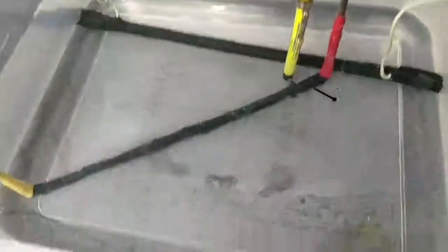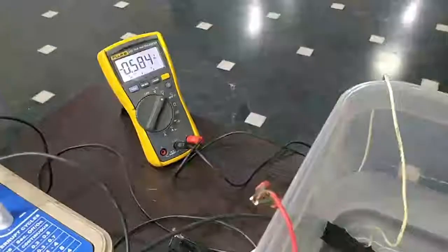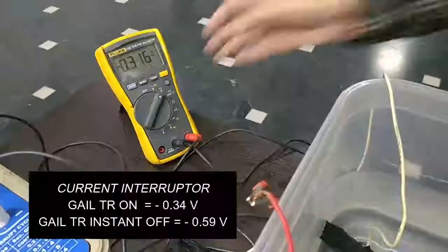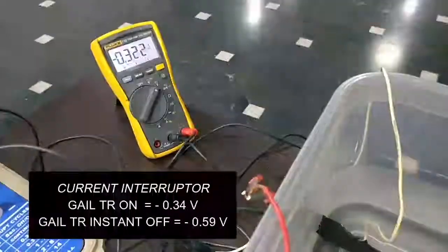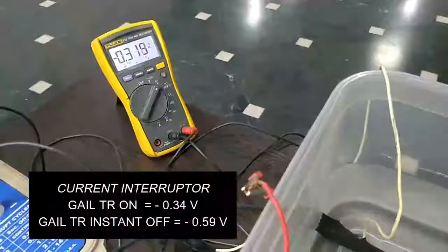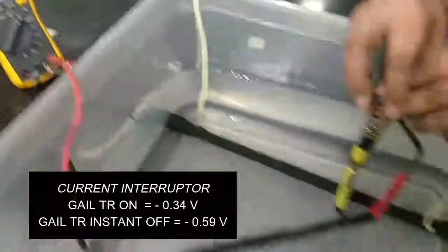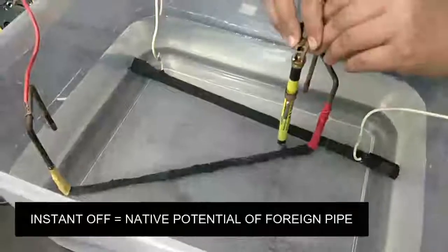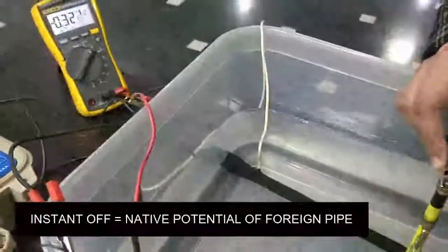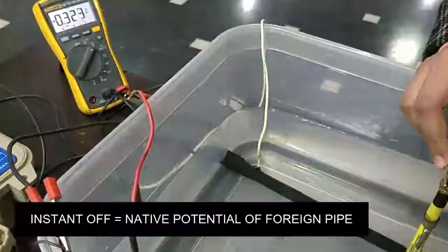Let's see what happens at the discharge location. At the discharge location, the on PSP value is minus 0.320 volt and the instant off PSP value is minus 0.58 volt. The instant off PSP value indicates that the potential is getting back to its native potential.